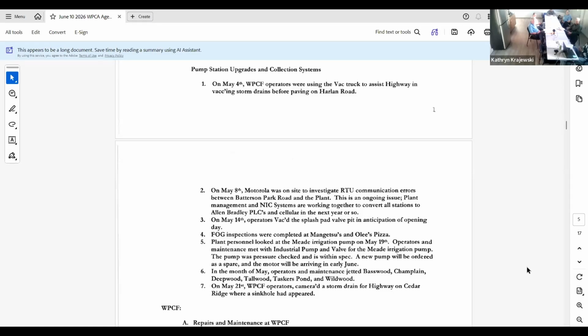On May 8th, Motorola was on site to investigate RTU communication errors between Batterson Park Road and the plant. This has been an ongoing issue over the years, nothing serious, but most of our pump stations are on radio control, which is an RTU. Any upgrade we do, such as Yukon or Hyde Road, uses cellular with a PLC like Allen Bradley. The radio works well, but foliage coming in the spring can hinder the signal since the antenna was positioned for winter conditions. So we're looking at upgrading some of them. Cellular seems to work better around here than radio. Coming up the road from West Farms, you have a lot of topography, so we're always trying to get the antennas a little higher to help with that.